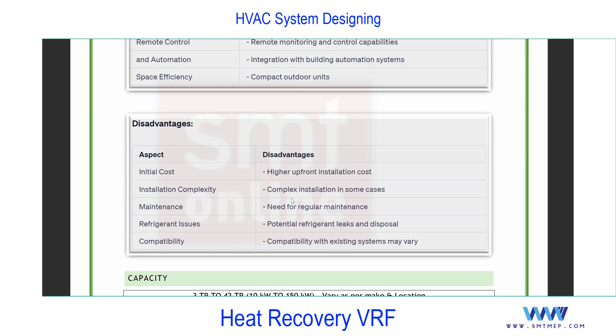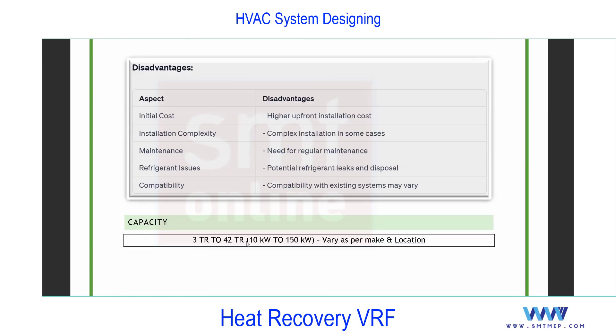In case of refrigerant leakage from one unit, it may affect the whole system — another disadvantage compared with other systems. Regarding capacity: VRF systems are generally available from 3 TR to 42 TR. In catalogs you will find capacity listed in kilowatts, since both cooling and heating are involved. For heat recovery or heat pumps, the unit is TR, but in actual practice catalogs show kilowatts. Important conversion for interviews: 1 kilowatt equals 0.28 TR.